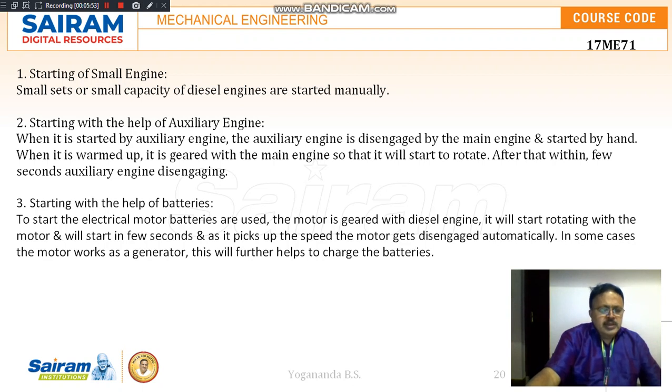Then the third method is starting with the help of batteries. To start the electrical motor, batteries will be used. The motor is geared with the diesel engine, so it will start rotating with the motor and start the engine in a few seconds. As it picks up speed, the motor will get disengaged automatically. In some cases, the motor will work as a generator, which will further help to charge the batteries fitted in the engine.